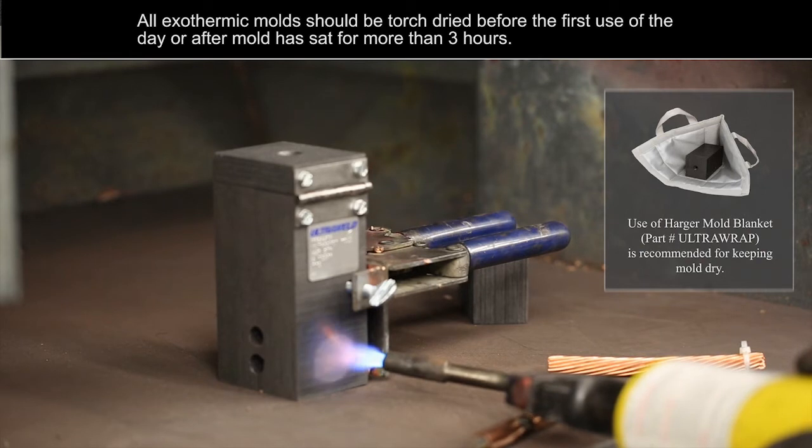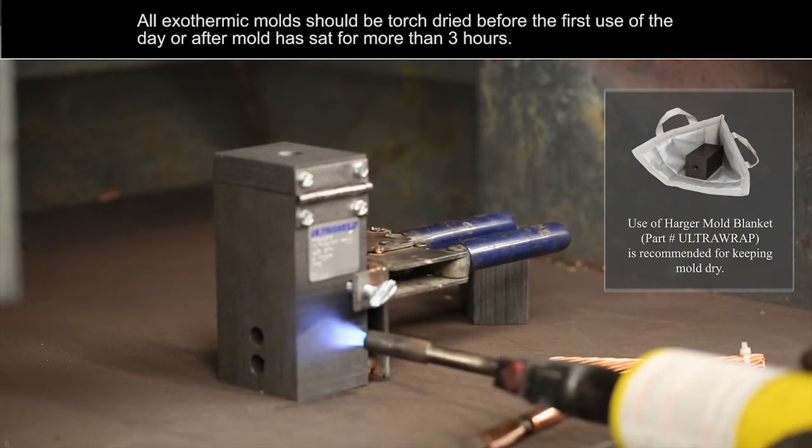All exothermic molds should be torch dried before the first use of the day or after the mold has set for more than three hours.